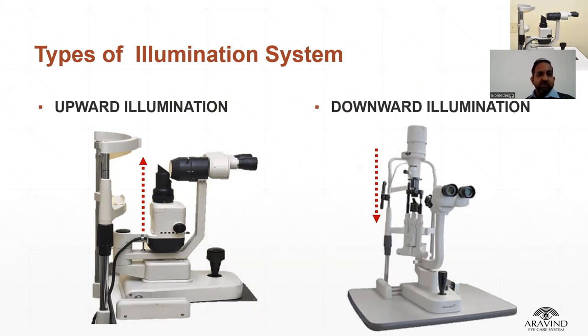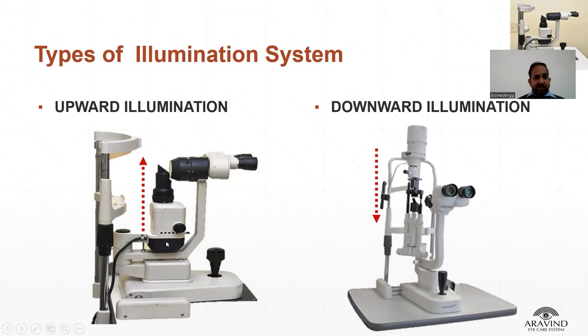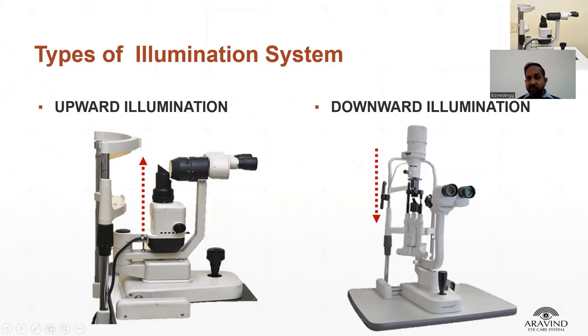The slit lamp is defined by two types of illumination system. The first one is the upward illumination system and the second one is the downward illumination system. In the upward illumination system, the bulb or light source is placed at the bottom of the slit lamp in the lamp house. In the downward illumination system, the bulb or light source is at the top of the slit lamp. The upward illumination system uses a right-angle prism to direct light into the patient's eye, and the downward illumination system uses a mirror kept at a 45-degree angle to direct light into the patient's eye.